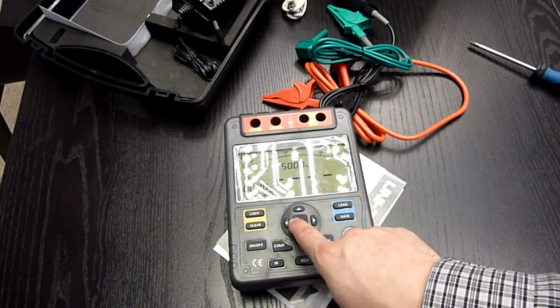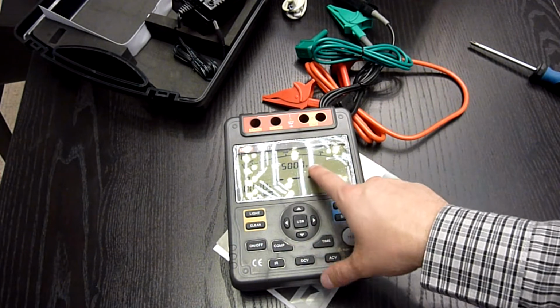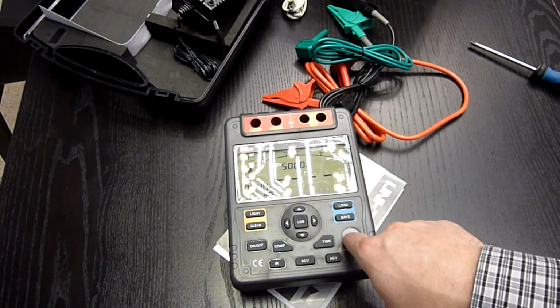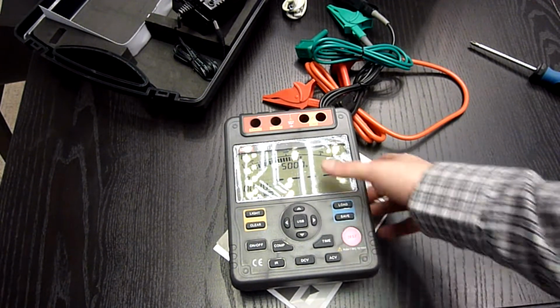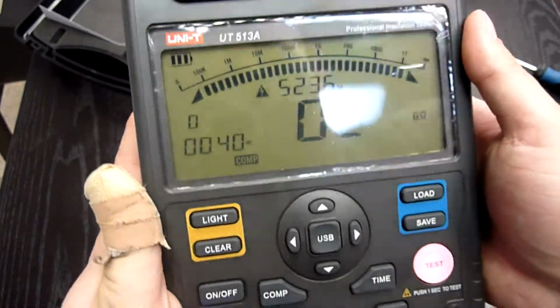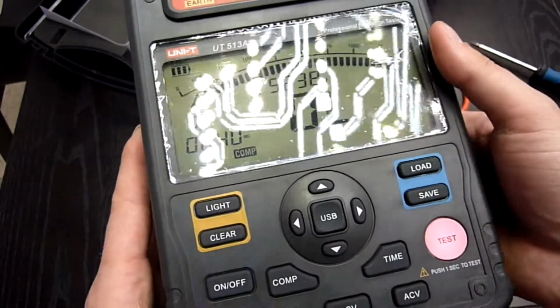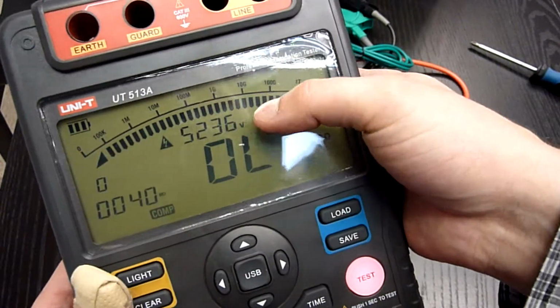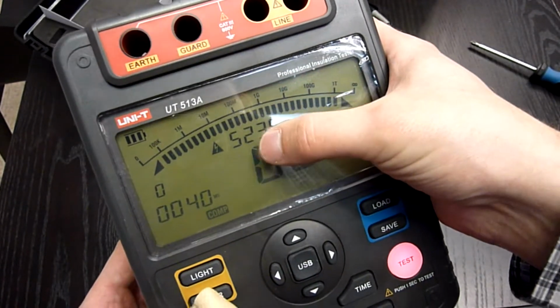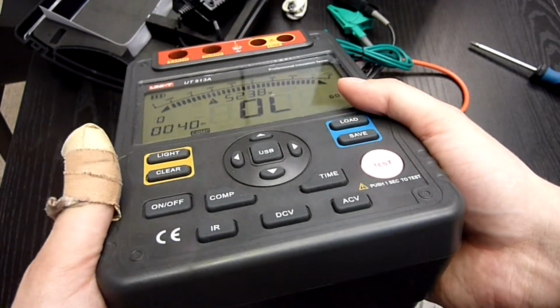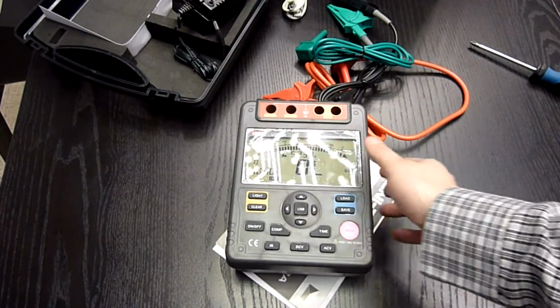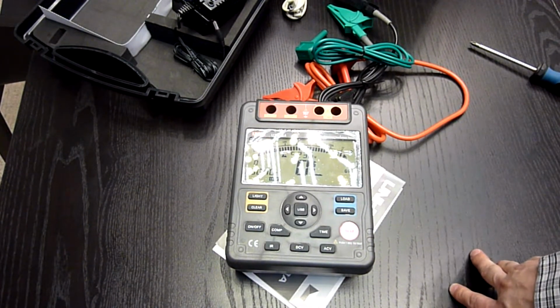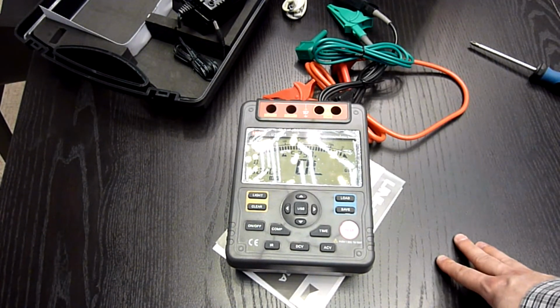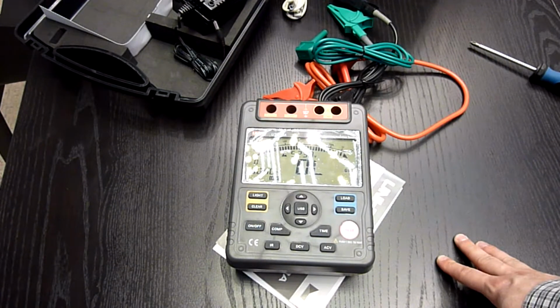And what I really like is that we can generate 5 kilovolts. Let's turn the test on. You can notice this button becomes red when the device is generating the voltage. Oh, we have nothing attached, so this is overload now. This is infinite resistance between the terminals, and we can see we have 5K and 230 volts on the output. Yeah, so perhaps now is the time to demonstrate how it looks when we go into short and how it performs during a permanent short.